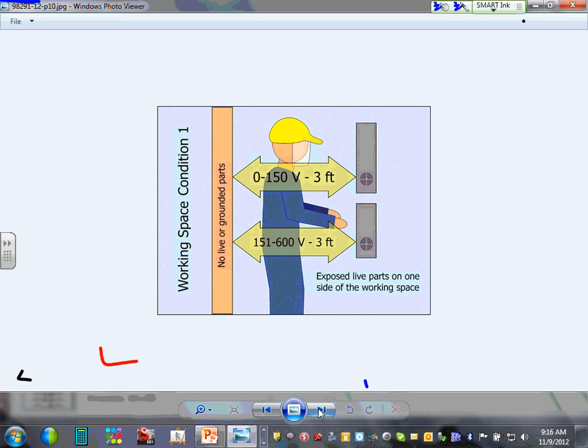In your panels, you have to label the panels with the full load current, the voltage, the interrupting current, the arc flash, the feeder that feeds the panel, and what else did we forget? And if it's a delta panel, you have to label it as a delta panel. Clearances in the front of the equipment. Right, I'm at a switchgear right in front of me, guys. You have to have from 3 feet minimum all the way to 4 feet, depending on the voltage, or if you have a sheetrock wall or a concrete wall or another panel in front of you. So it goes from 3 all the way to 4. Cool.